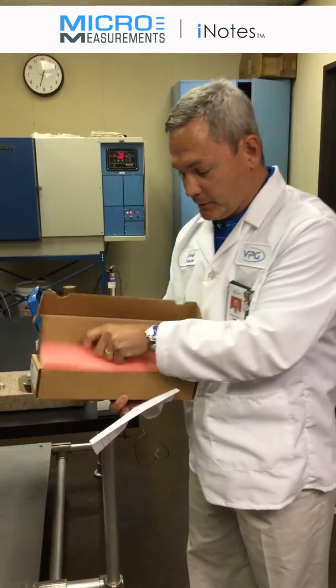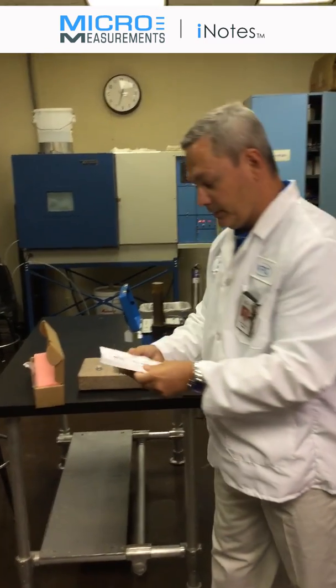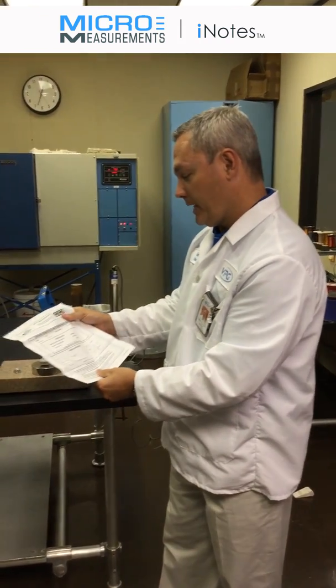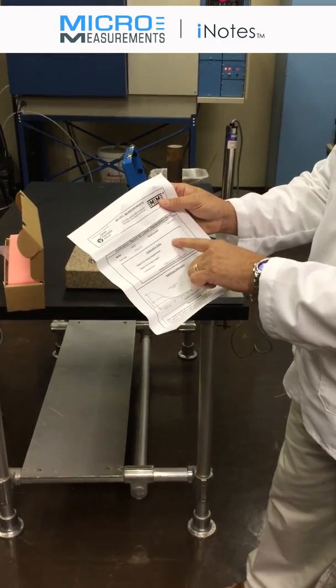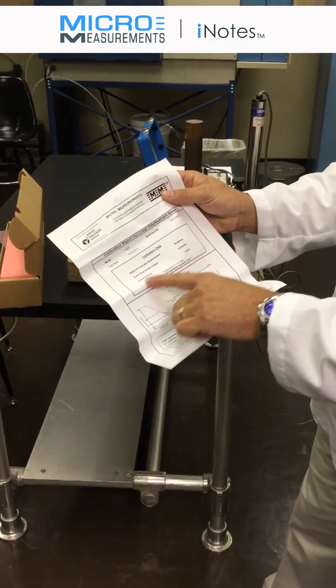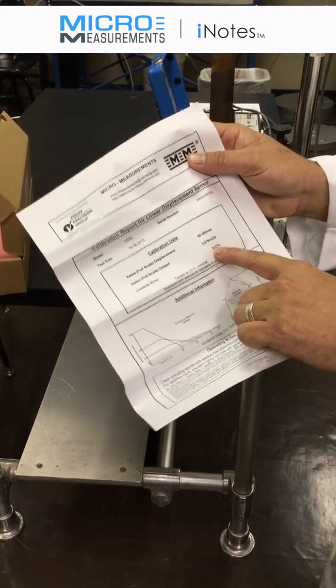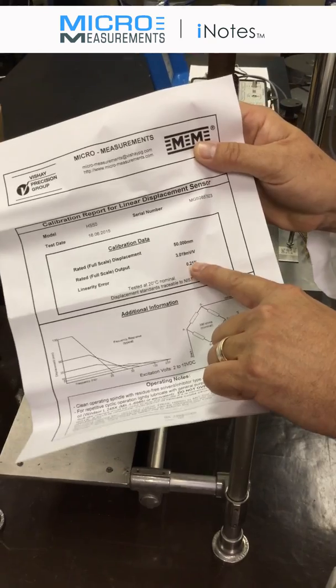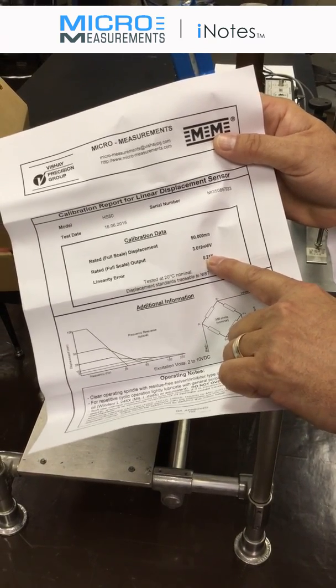In addition, in this box you also have one of our calibration data sheets. On this calibration data sheet, you'll find the full rated displacement as well as its rated output at that full displacement. Along with that, you'll also see its linearity error, and that's one of the advantages to using these HS series sensors—they have a very nice linear region. In this particular case, 0.21 percent.